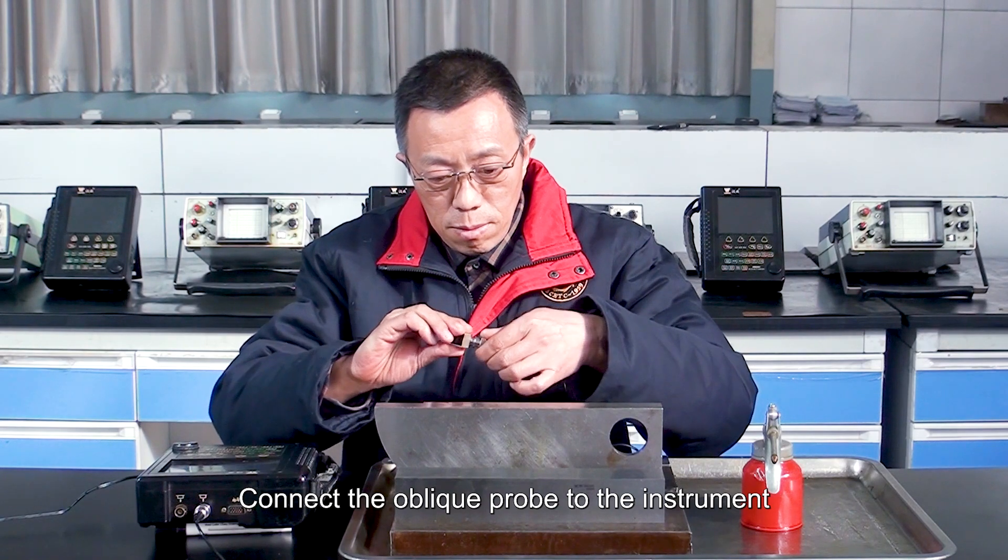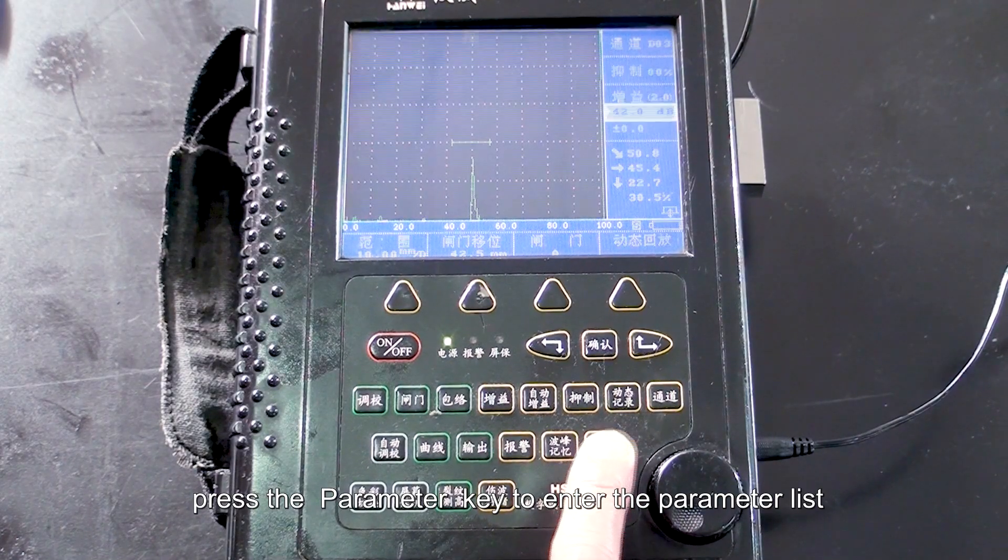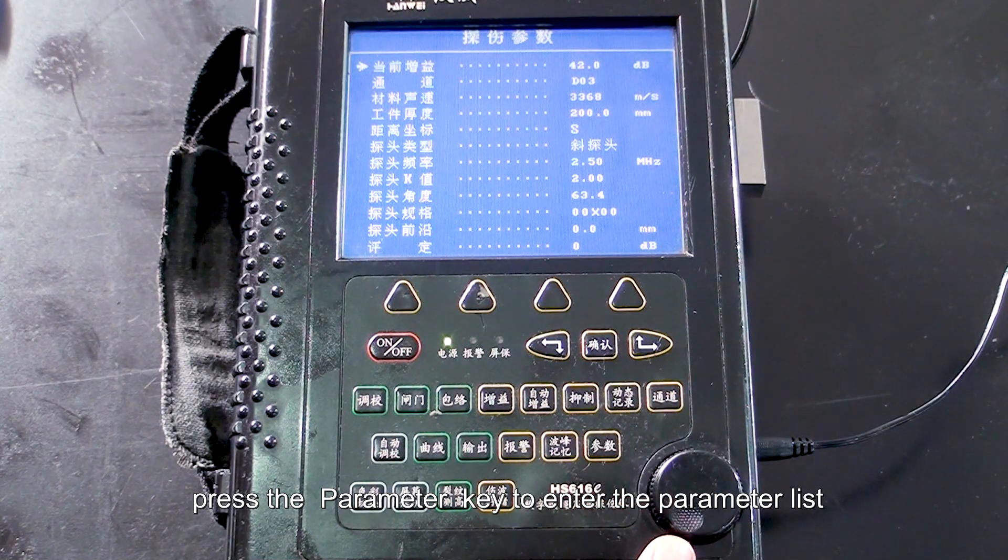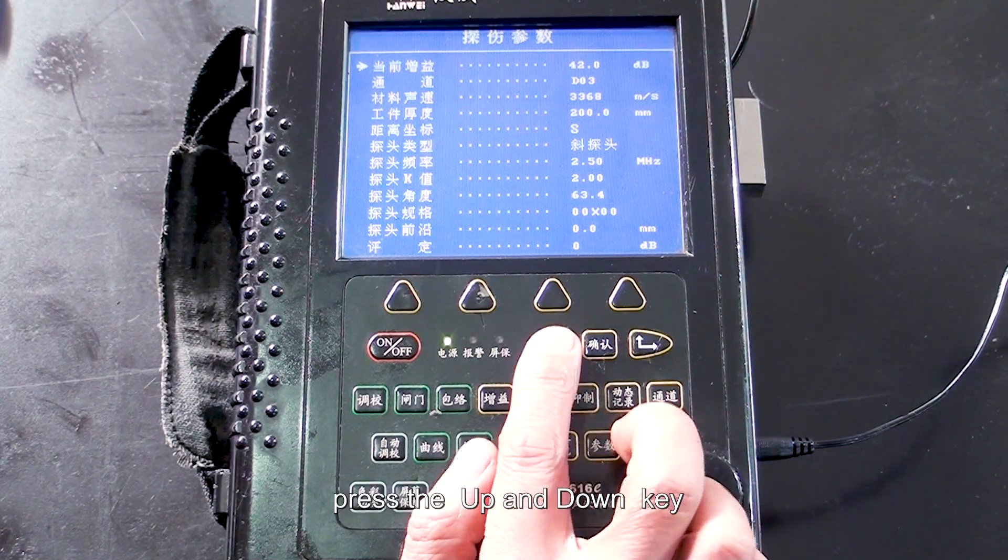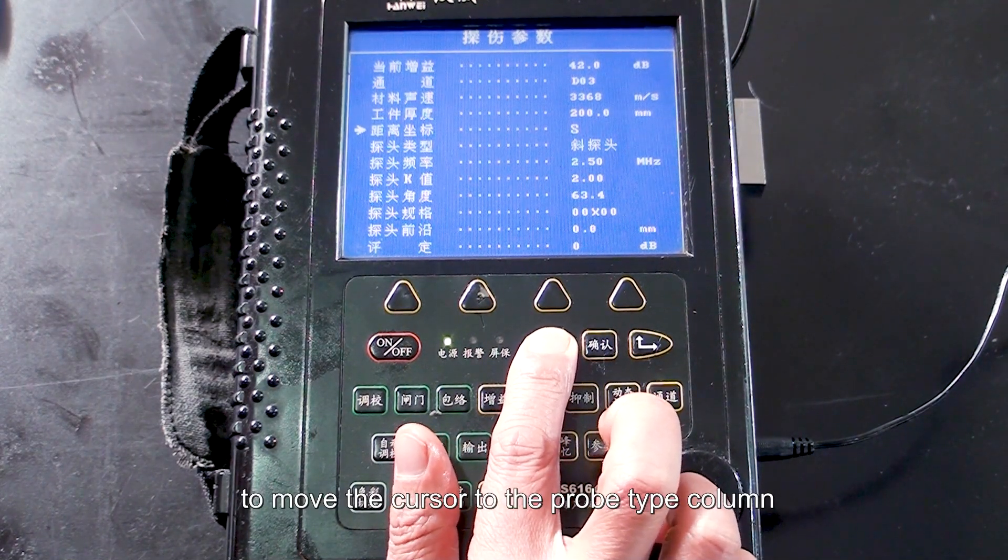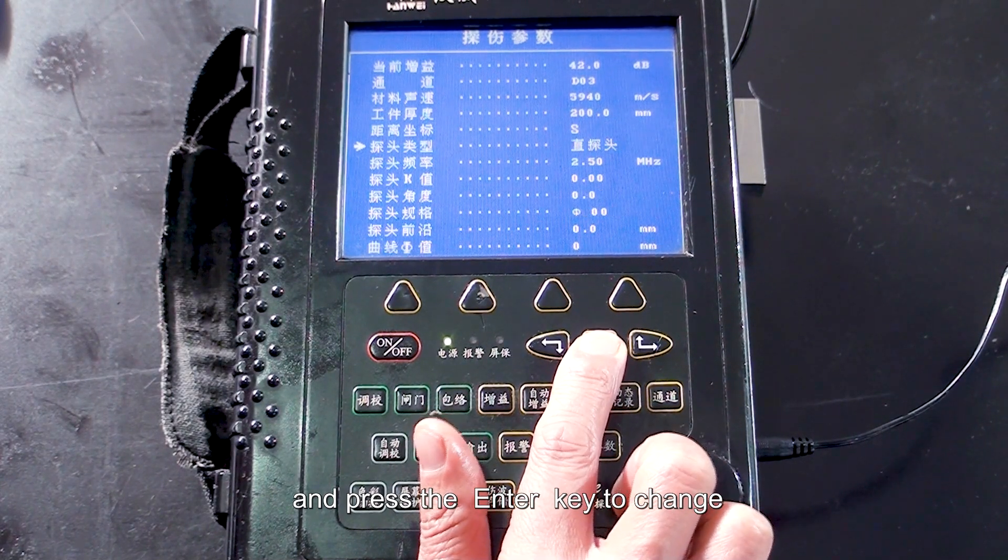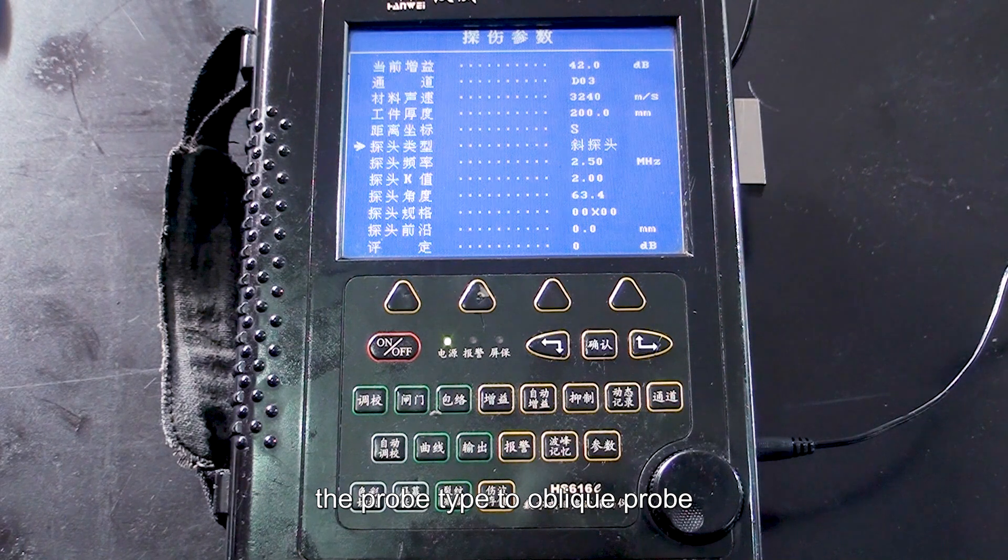Connect the oblique probe to the instrument, press the parameter key to enter the parameter list, press the parameter key to move the cursor to the probe type column, and press the enter key to change the probe type to oblique probe.